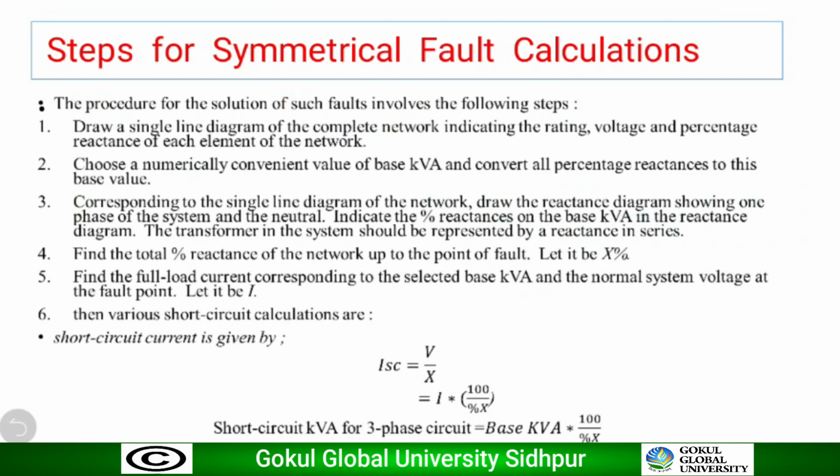Third, corresponding to the single line diagram of the network, draw the reactance diagram showing one phase of the system and the neutral. In the symmetrical fault calculation we consider only a single phase because all the phases have the same magnitude of short circuit current and the same phase displacement. Indicate the percentage reactance on the base kVA in the reactance diagram. The transformer in the system should be represented by a reactance in series.